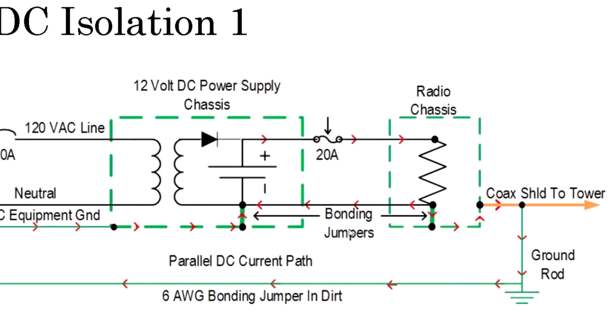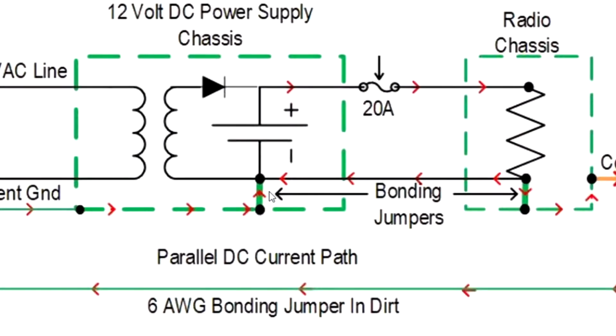That causes us a couple of issues. One, if you've ever wondered what the 60 hertz hum in your transmit and receive audio is, this is a good source of it. The other thing it does, by running DC current with a negative polarity, is cause corrosion to all our ground electrode system buried down here in the dirt. You've got moisture and acidic conditions, and it just sets up the perfect conditions for corrosion.